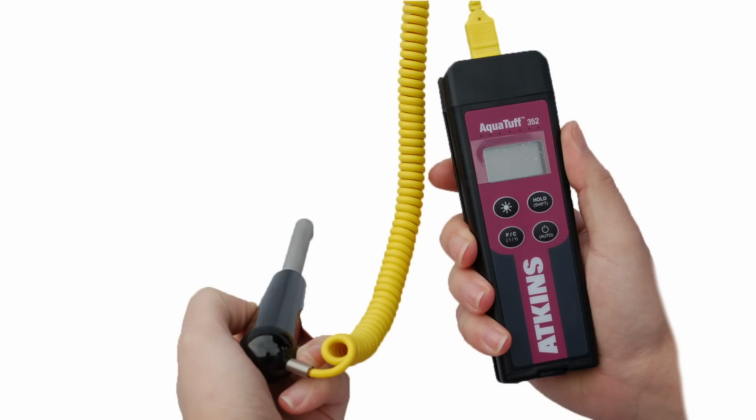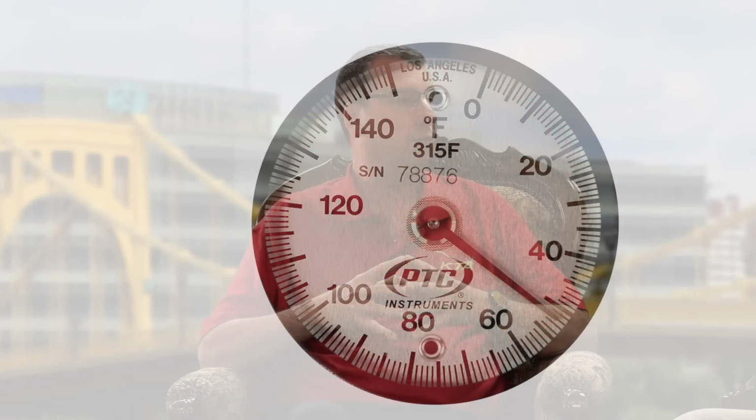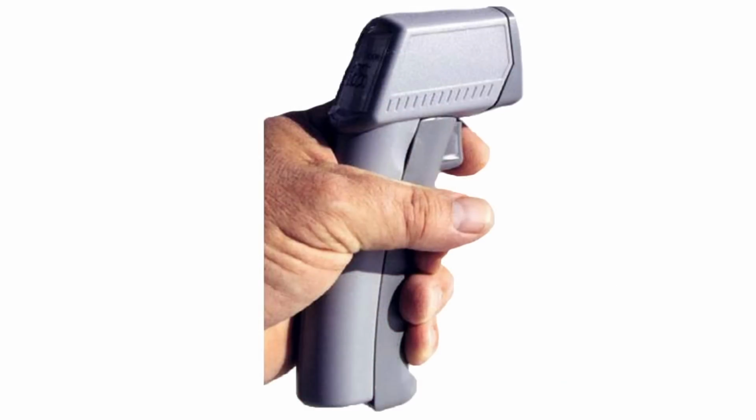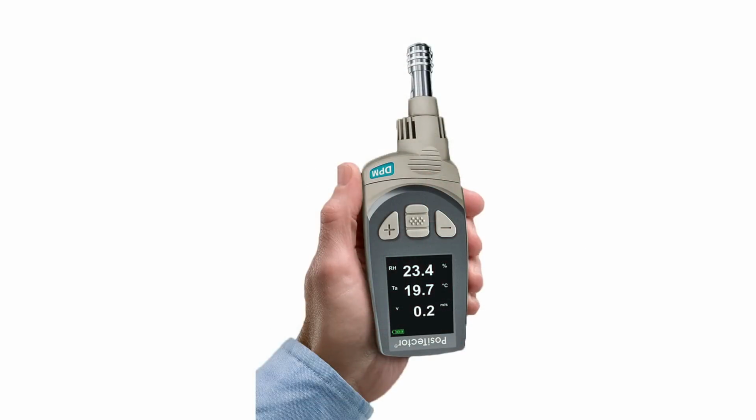Okay. Another question, we compare surface temperature with dew point. With the sling psychrometer, there's no surface temperature integral to it. Correct. So you get a separate gauge. What about for the digital equipment? So with the whirling psychrometer, you have to have a separate instrument, either a thermocouple type or a dial type thermometer to measure surface temperature. And some people even use some non-contact infrared pyrometers for that. With the digital psychrometers, most of them come with a built-in surface temperature probe. That can also be non-contact infrared. And some of the digital psychrometers also come with a hot wire so you can measure wind speed as well.